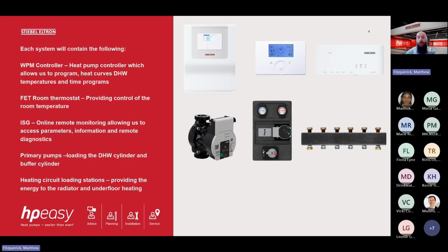In the top right, we have what we call our internet service gateway. Now, this is remote monitoring. It's a remote connection to the heat pump system. This will allow us to remotely diagnose the heat pump system. It will allow us to change any parameters remotely, see if parameters have been changed at the controller, and revert it back to its commissioning parameters with the click of a button. It's exceptionally useful and time-saving because you don't need or require an engineer to go to site for every given inquiry. You can look online. So it's vitally important to ensure in this day and age that your renewable system has some form of remote monitoring, remote logging to be able to access the system without having to go to site.